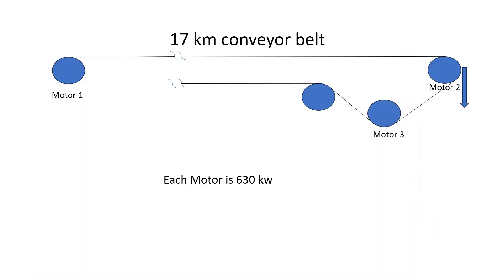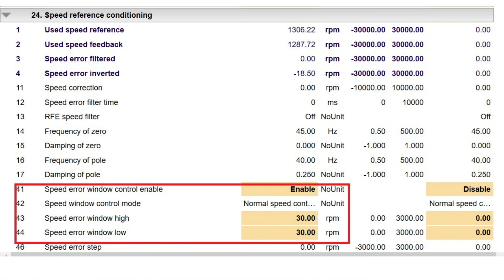If you have equipment coupled flexibly, like this conveyor belt, then you can use speed control mode. Because there is a provision that allows some speed difference, like 10 RPM — since this is a flexible coupling, some tension variation can be allowed.